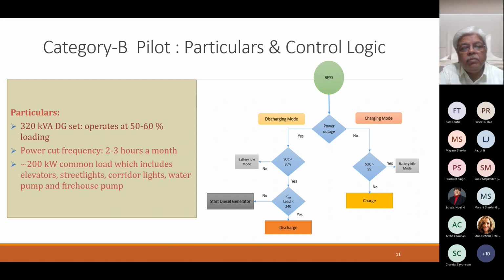One important component is that there are 192 flats in this complex, and every flat has about 1 kVA load supplied through the diesel generator set. If we add that, the load may go beyond the limit, which is why there is a second decision box: if the load exceeds a certain limit, one has to go to the diesel generator set rather than through battery supply.